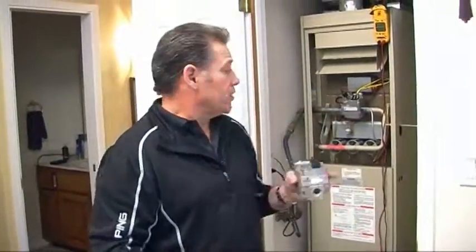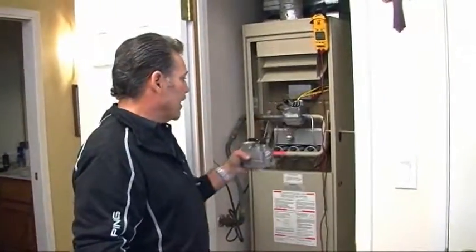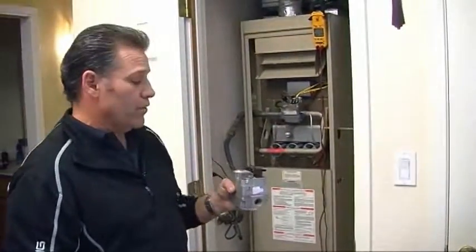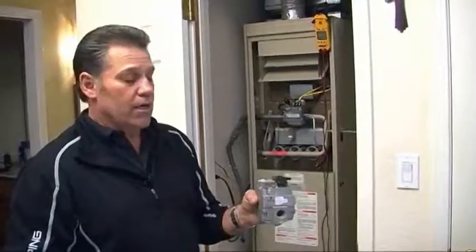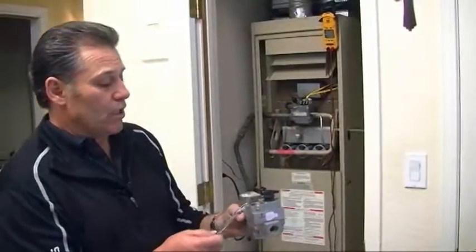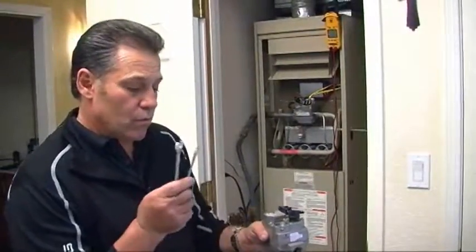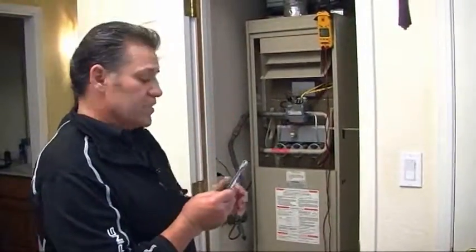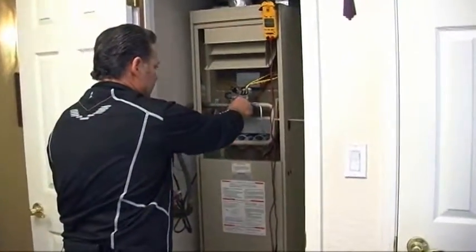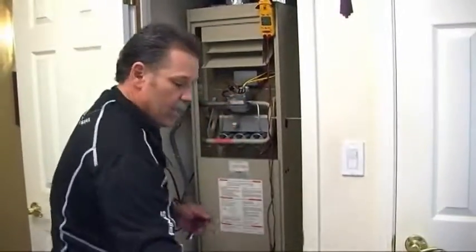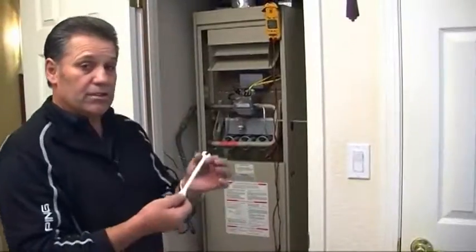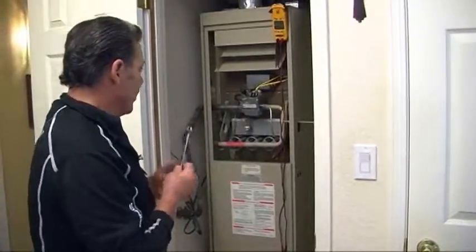Okay, earlier today I replaced the gas valve and the thermocouple on this Lennox 80% atmospheric furnace. There are two wrenches you're going to need when you're working with the pilot assembly. One is a 7/16 inch open end wrench, which fits the nut for that. The other is for the thermocouple. It's a 3/8 inch open end wrench.